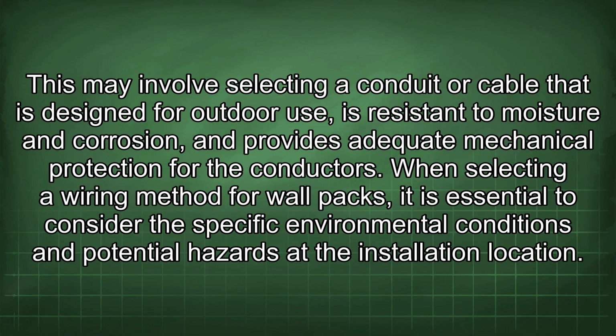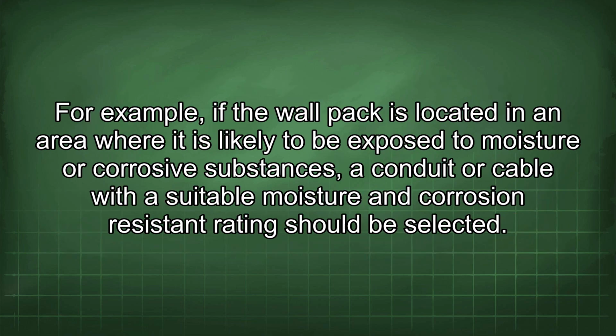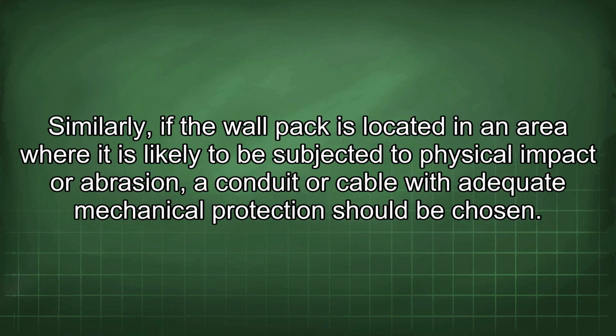When selecting a wiring method for wall packs, it is essential to consider the specific environmental conditions and potential hazards at the installation location. For example, if the wall pack is located in an area where it is likely to be exposed to moisture or corrosive substances, a conduit or cable with a suitable moisture and corrosion-resistant rating should be selected. Similarly, if the wall pack is located in an area where it is likely to be subjected to physical impact or abrasion, a conduit or cable with adequate mechanical protection should be chosen.